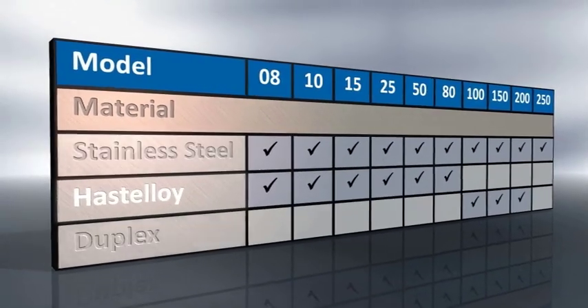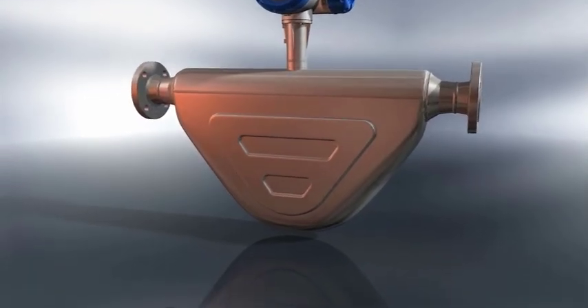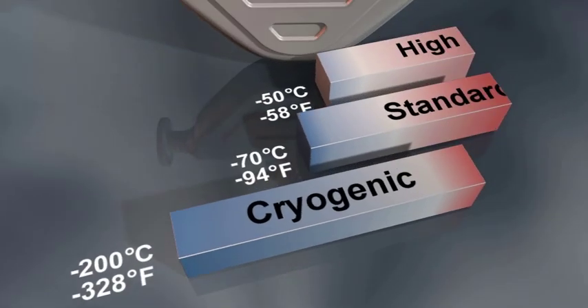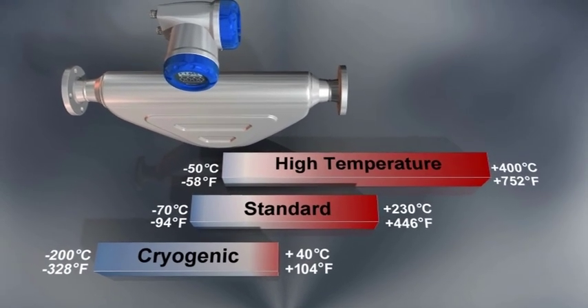The meter is available from sizes 08 to 250, in three materials: stainless steel, Hastelloy and duplex, and with NAMUR installation lengths. The stainless steel version is available in three types — cryogenic, standard and high temperature — all pressure rated at 100 bar, 1450 PSI. The Hastelloy and duplex high pressure variants are rated at 200 bar, 2900 PSI.